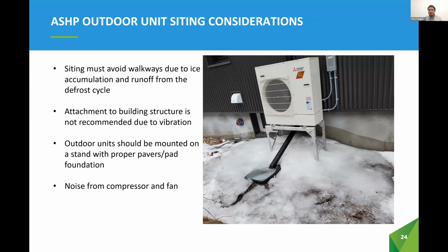Here are some siting considerations for air source heat pumps. Firstly, the outdoor unit must be carefully considered. The location of the outdoor unit must be carefully considered due to ice accumulation and the runoff from the defrost cycle. Attachment to building structure is also generally not recommended due to vibration, and instead, outdoor units are ideally mounted on a stand with proper vibration isolation and a proper foundation. This stand also helps with the ice accumulation, which was mentioned above, as well as natural snow accumulation in our climate. Noise from the compressor and the fan should also be considered.